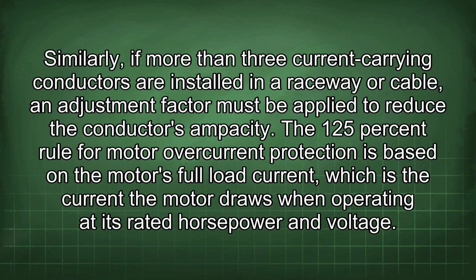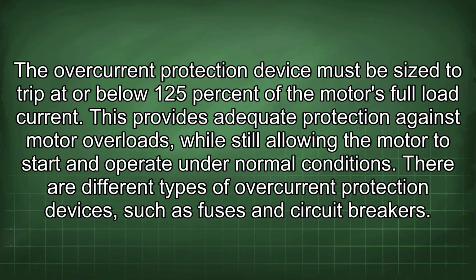Similarly, if more than 3 current-carrying conductors are installed in a raceway or cable, an adjustment factor must be applied to reduce the conductor's ampacity. The 125% rule for motor overcurrent protection is based on the motor's full load current, which is the current the motor draws when operating at its rated horsepower and voltage. The overcurrent protection device must be sized to trip at or below 125% of the motor's full load current. This provides adequate protection against motor overloads, while still allowing the motor to start and operate under normal conditions.